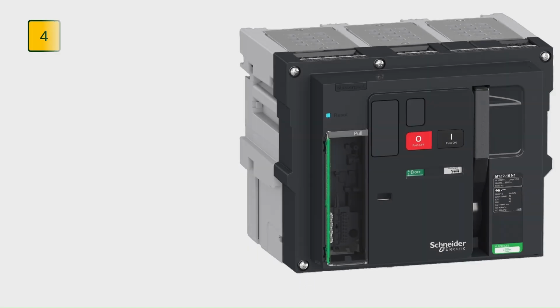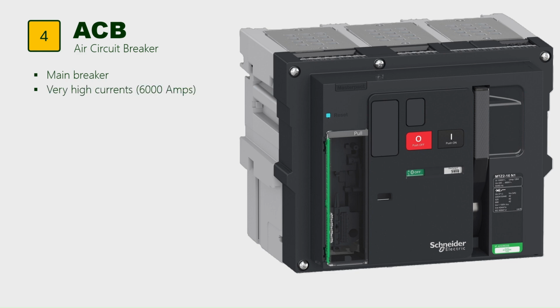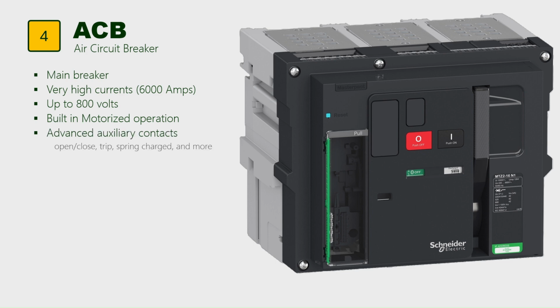And finally, the ACB, Air Circuit Breaker. This is the main breaker you'll find at the bottom of large LV panels, data centers and industrial switchgear. ACBs handle very high currents, often up to several thousand amps, and they also work up to 800 volts. Almost all ACBs come with motorized operation built in, so you can open, close and reset them remotely. They also have advanced auxiliary contacts that show open close status, trip cause, spring charged status and more.